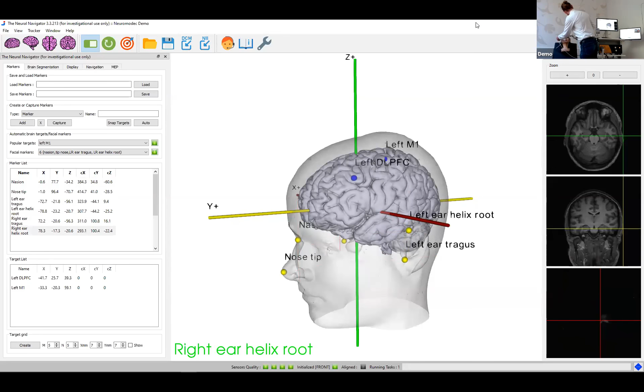So we'll ask you to capture all the different markers on the patient's head. And when this has been done successfully, it will also show you that the alignment was performed successfully. If you, for example, captured one of the markers in the wrong position, there's a possibility to go back and recapture a marker. But now everything was done successfully, and that means that the software will start to stream the position of the TMS coil automatically. So we already see it hovering over the patient's head.